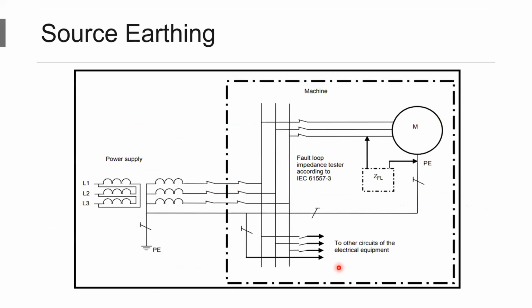Now, before we talk about the fault loop impedance, let us also understand, like Mr. Gopakumar was also explaining earlier, in case of IS 14665, two separate earthing pits have been called for, which has been a mistake in the past and has become a practice in the industry, which in itself renders that particular installation as TT, and we are trying to do a fault loop impedance test over there, which fails. And why is this happening? This is important because the understanding is that the fault loop has to go back to the source.